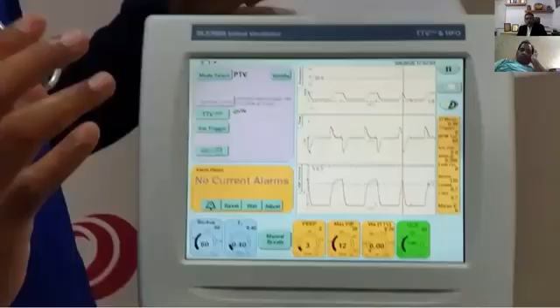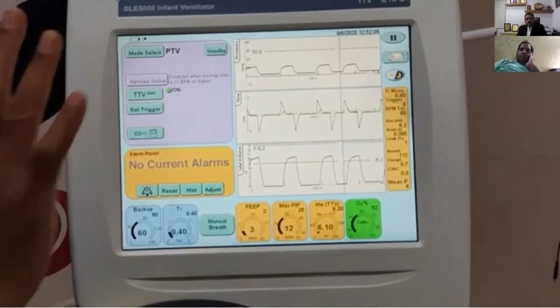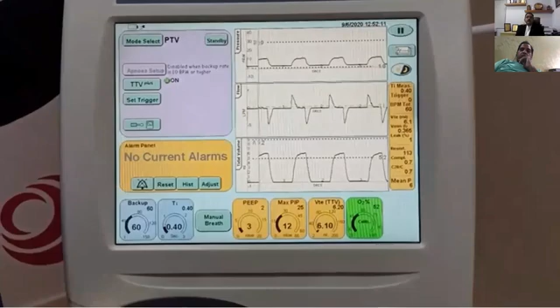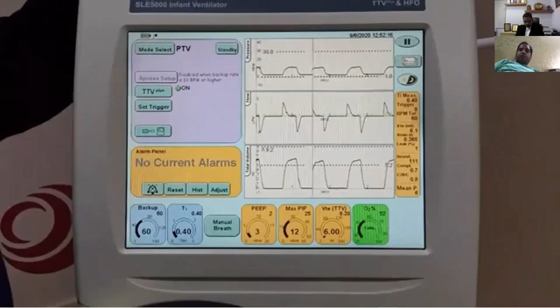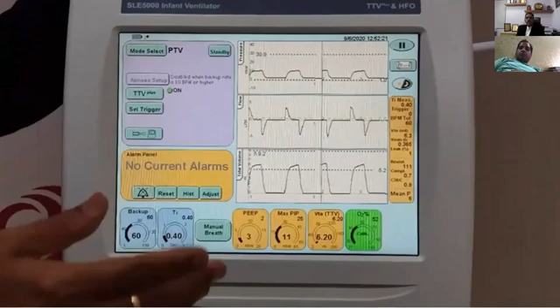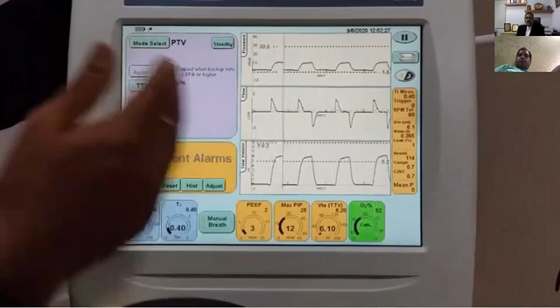The most important is the leak, because especially when you are doing volume guarantee ventilation or targeted tidal volume ventilation, it is very important to have the leak below 20%. Even though these ventilators are geared to overcome a leak of 50%, generally you will not be able to give effective tidal volume if the leak is around 50%. Generally, what is recommended is, if it is above 20%, better to re-intubate with a bigger size tube and continue with the volume guarantee ventilation or targeted tidal volume ventilation.